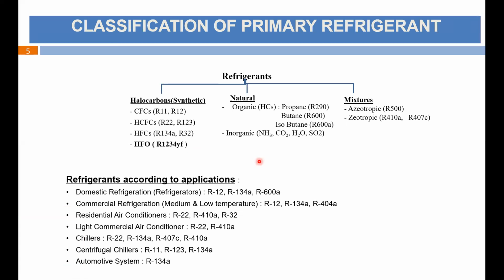They are again further classified in four categories: CFC, chlorofluorocarbon. As you know, R11, R12, these are all historic refrigerants. Nowadays, these are not used. Second is HCFC, that is hydrochlorofluorocarbon, which is R22, R123. These two refrigerants are almost in the phase out stage as per the Montreal protocol. I'll come to the details in the later slides.